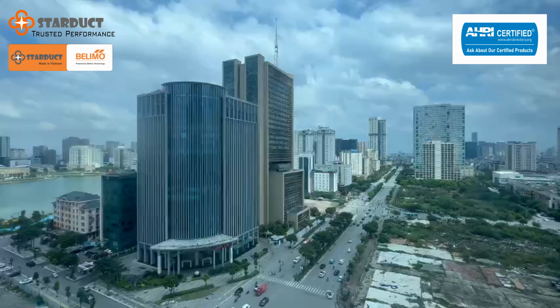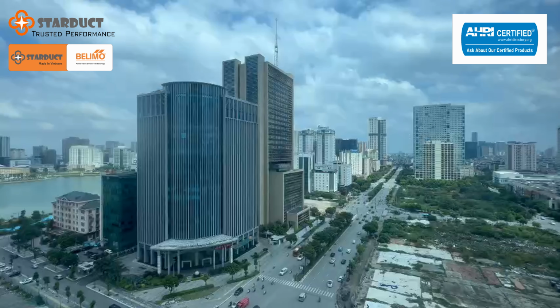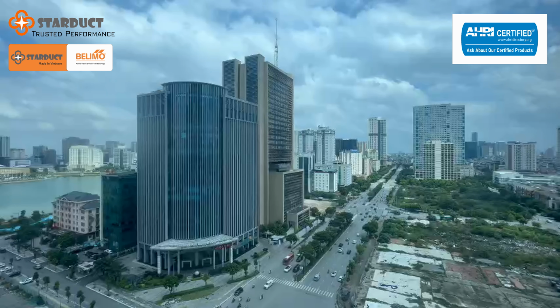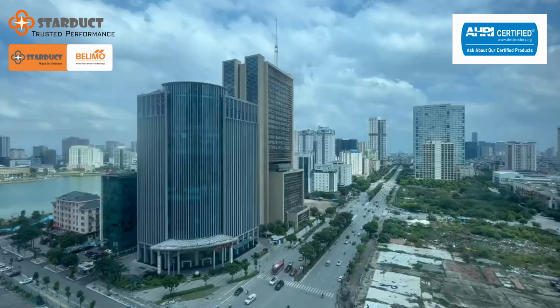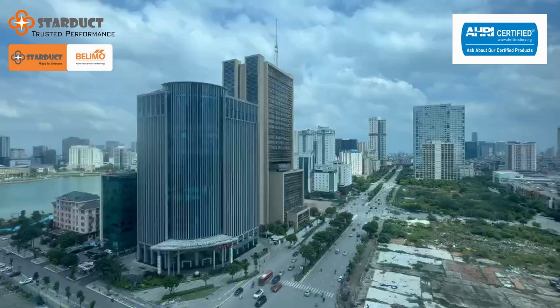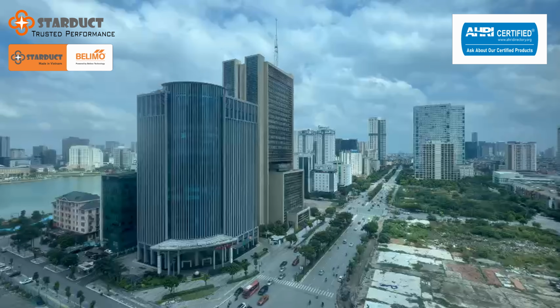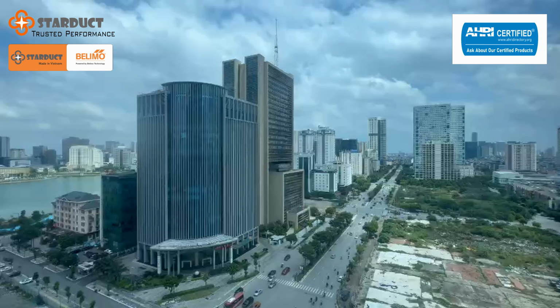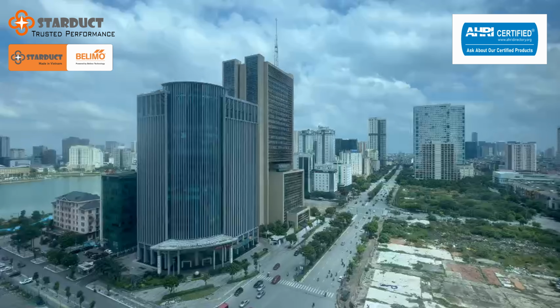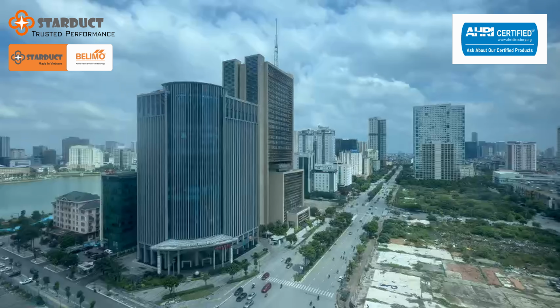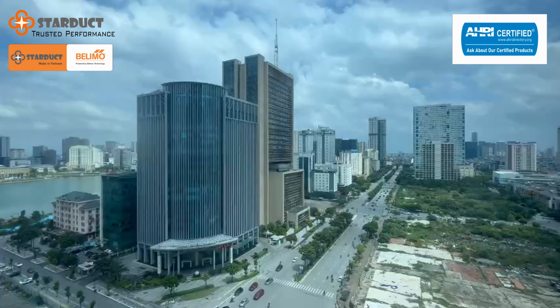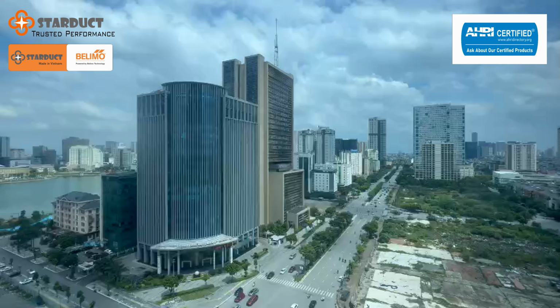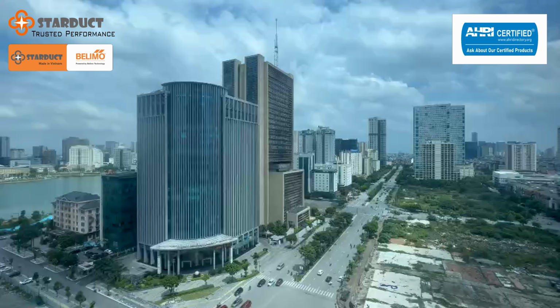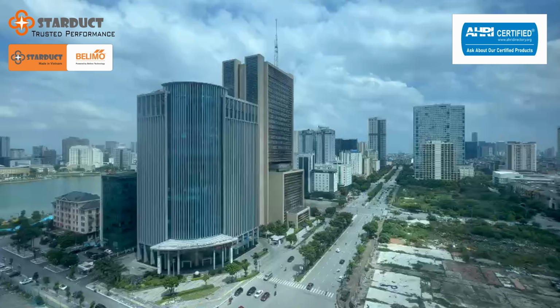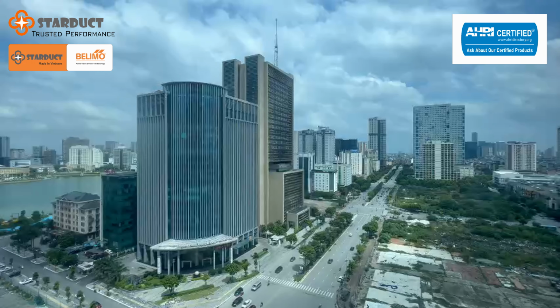All right, let's pivot slightly then. Let's talk about the core input variable here, the delta P signal itself. Its integrity is absolutely central, regardless of whether you prioritize the K factor or the field measurement. Yes, exactly. Because the whole formula Q equals K times the square root of delta P completely falls apart if that delta P measurement itself is bad. And field experience, unfortunately, shows us plenty of ways it can go wrong.